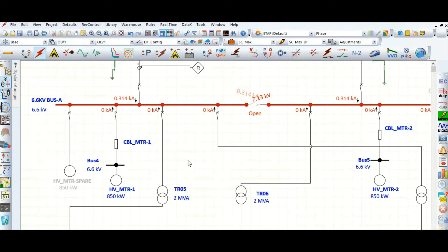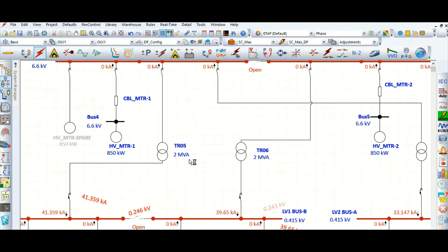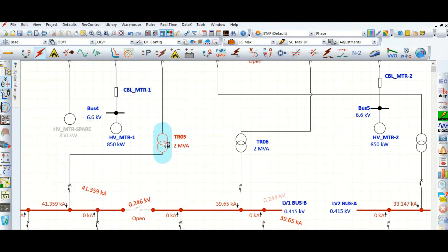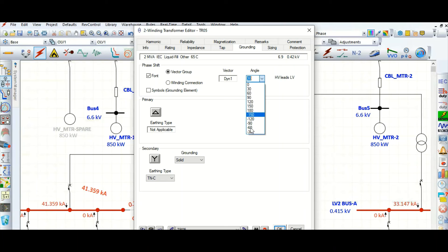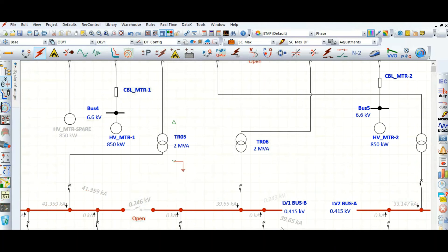Let's check the LV distribution transformer. Go to the grounding tab, change the vector group to Dyn11 by setting minus 30 degrees, check the symbol. Here delta-star — star is solidly grounded because this is a 415 V system and I want it solidly grounded. From the symbol you can also confirm this is solidly grounded. Let's run IEC 60909 again.